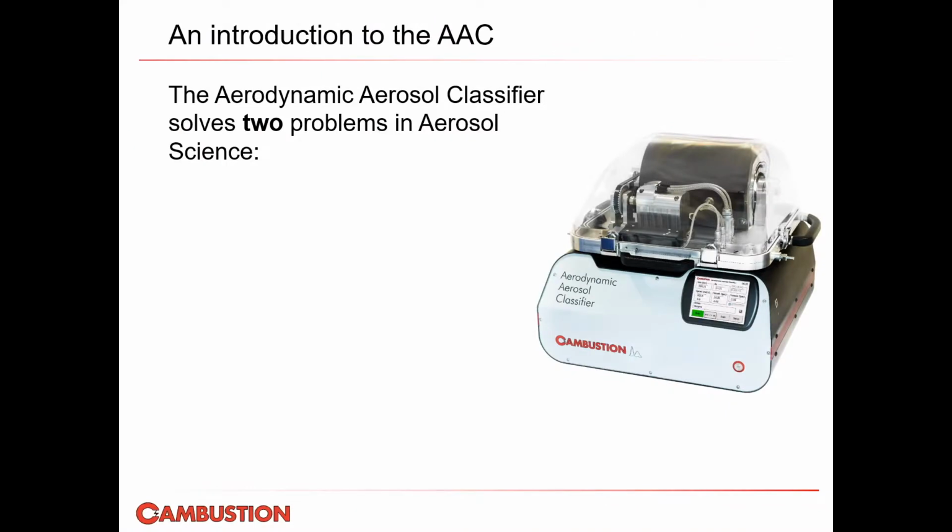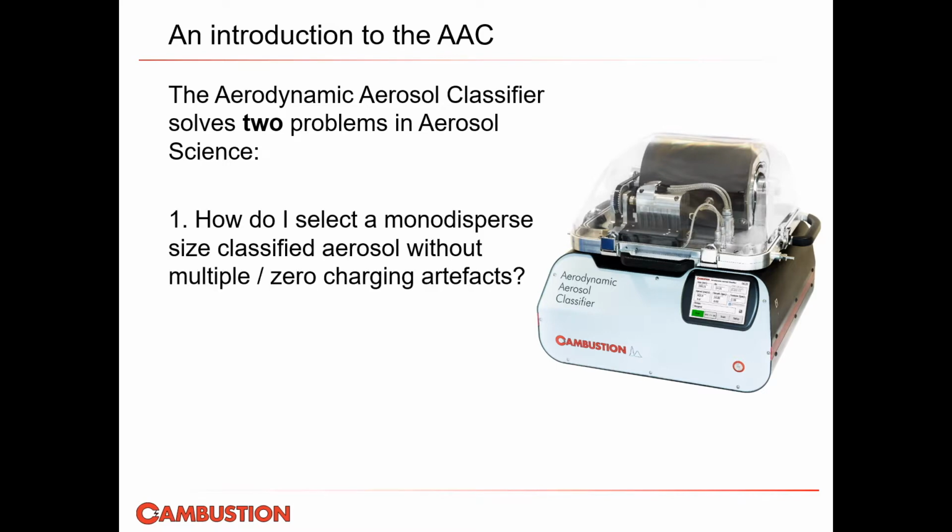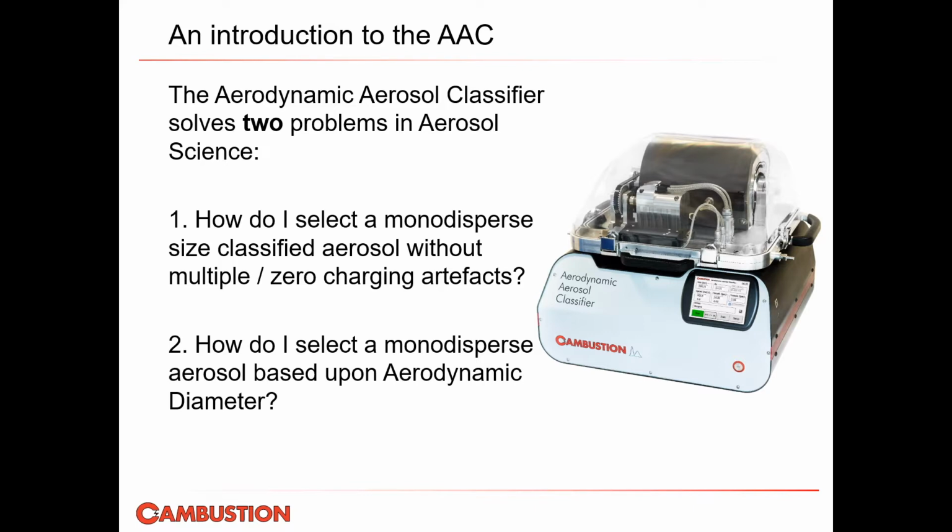The aerodynamic aerosol classifier, or AAC, solves two problems in aerosol science. The first is, how do I select a monodisperse size classified aerosol without multiple charging or zero charging artifacts, as you may get with the DMA? The second is, how do I select monodisperse aerosol based upon aerodynamic diameter, if that's my metric of choice?